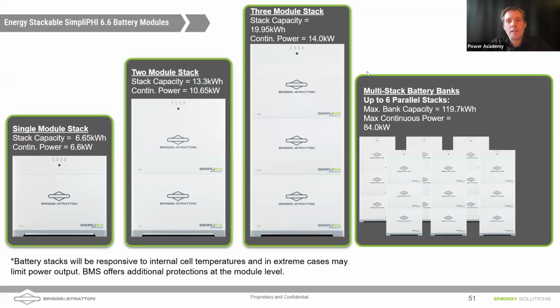Some nice features of the battery. Overall, you can put a total of 18 batteries together in a bigger system. So if you have a really large system, 120 kilowatt hour system, keep in mind you're only allowed to install up to 80 kilowatt hours in a garage. But if you have a detached building, or the ability to do some outside, some inside, then you could do a really large system like that. But do follow the code. And for a single stack of batteries for smaller systems, we can do 6.6 kilowatts out of a single battery. Can do 10.5 kilowatts out of a 2-stack, and out of a 3-stack, we can do 14 kilowatts of continuous power.